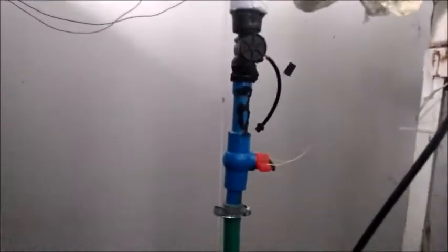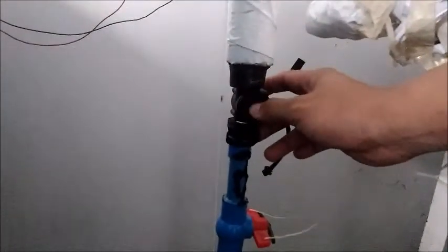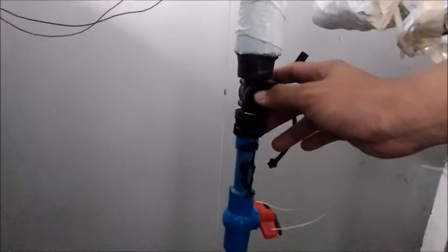Also, we have provided hose so that anyone who will clean the pump can easily remove the pipeline connecting to the fan coil unit and the chilled water tank. Also, we have provided a new water flow sensor because the old one broke down due to the mixture of corrosion and brine.